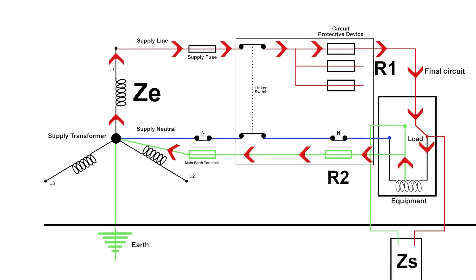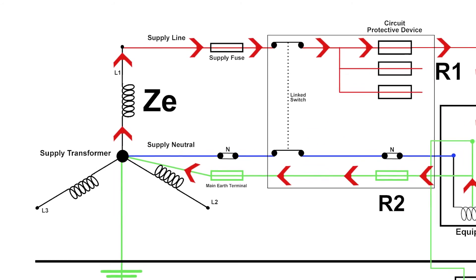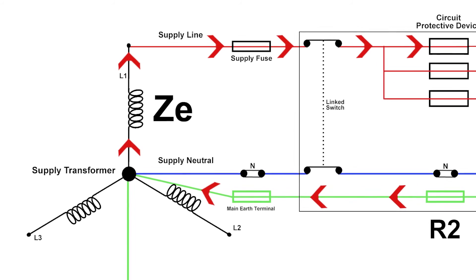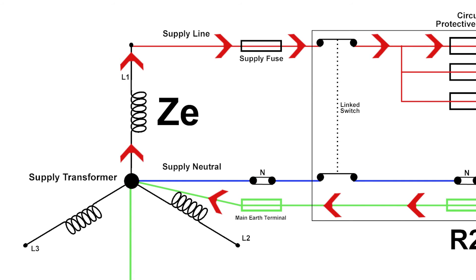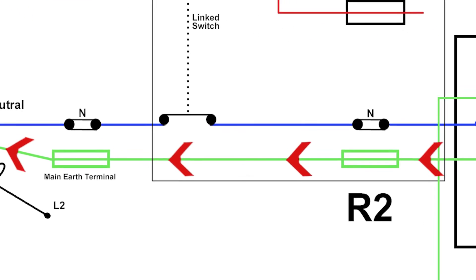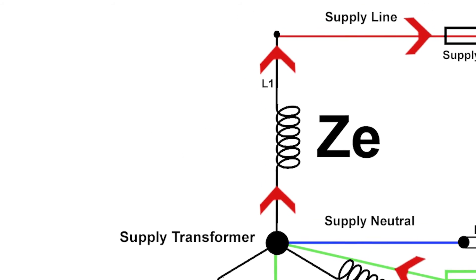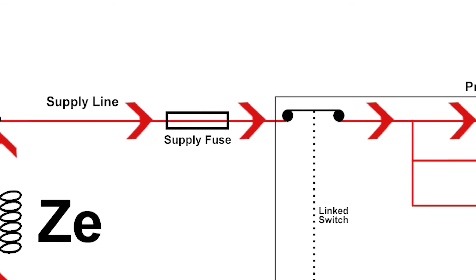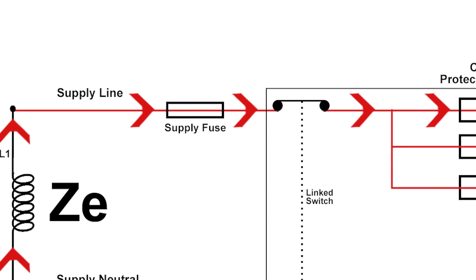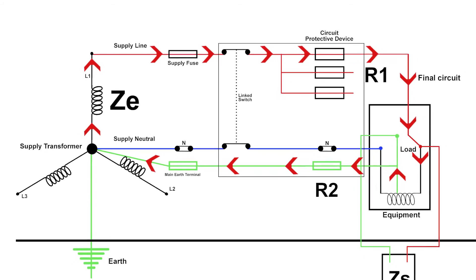So our earthing system is made up of really three components. We've got ZE, the E would be for external, Z is for AC resistance or impedance. So the resistance of our supply earth and supply line would form our ZE. If we wanted to measure ZE, we would just measure from our disconnected earth at the earth terminal, the main earth terminal, round to our incoming line on our main switch. That would give us ZE, but it's important at that point to disconnect the earth. You can see how to do that test in the other videos.